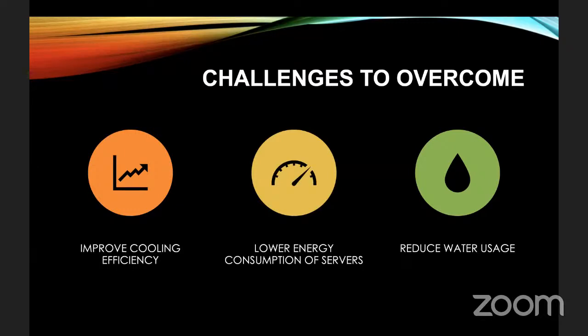Another challenge, though, with liquid cooling is solid state hard drives need to be used because the traditional magnetic spinning disks won't work in immersion cooling systems. So this is a technology that's coming through, but it's going to require a lot of effort and change of mindset by the data centers to really adopt it. And it's something that possibly we're not going to see really taken on board on a large scale for possibly another 10 years, because of the kind of cycles that the data centers go through before they're ready to start actually taking out old equipment and putting new in. But that's a surefire way of improving the efficiency of the cooling system.